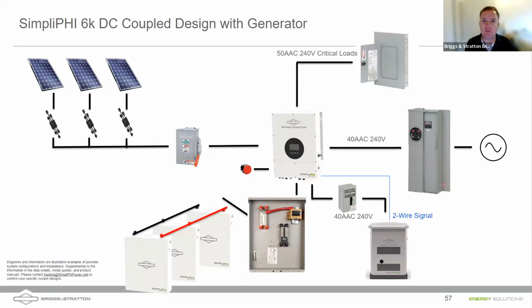This is what it can look like, right? So what do we have on the right? We have a grid going into our meter main with non-backed up loads. We're feeding that into our bidirectional 40 amp grid port. Why it's a 40 amp port is because by having it only be a 40 amp breaker, we're able to land that 40 amp breaker inside of this load center that has a 200 amp main with a 200 amp bus and stay within our 120% rule. Flowing up out of the inverter through our load port is going to go to our critical loads subpanel.